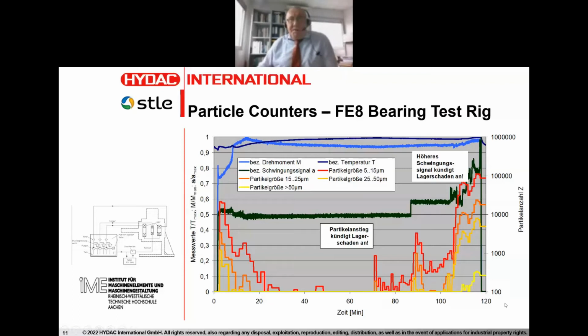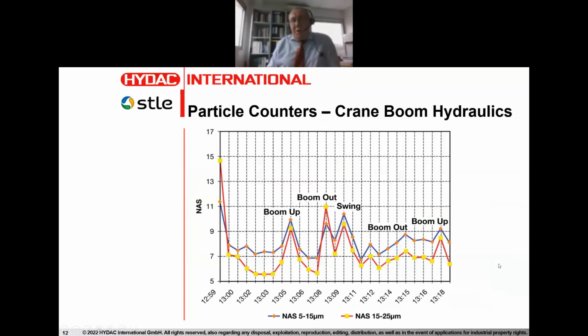So here, since this is a test rig, we can induce damage, if you will, and we can force the bearing to fail, and then we can see what is the result and how the bearing responds to the induced failure and how this induced failure manifests itself in the increase in particle counts. Another case was what happens when the system is being flushed out, as it were, when we're moving the boom around on crane boom hydraulics. So if we move the boom up and down, we swing it out, we move it out, we can see what happens to the particle counts.